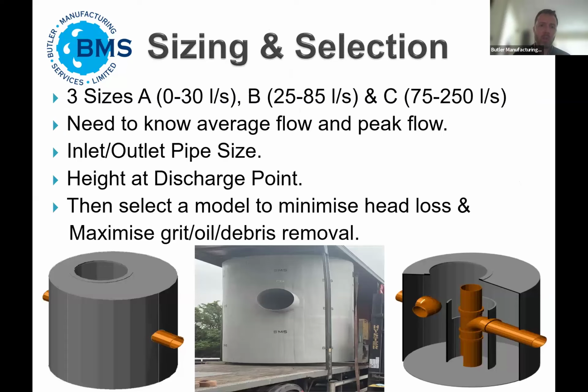And how do you size them? Well, there's three different sizes basically. There is a size A, which can do up to 30 liters per second, B up to 85 liters per second, and C up to 250 liters per second. And they're all custom selected based on the average flow and peak flow, the inlet and outlet pipe size, and the height at the discharge point.